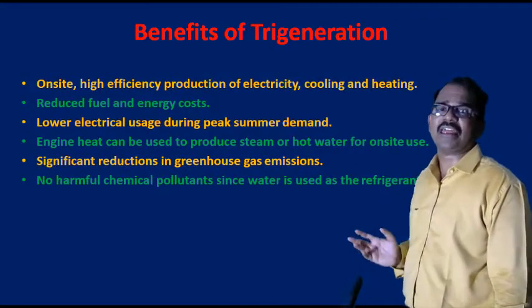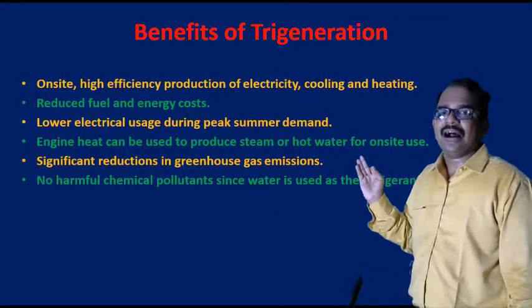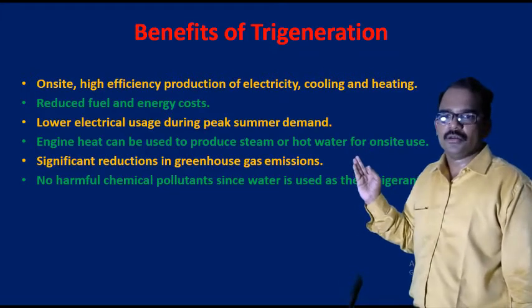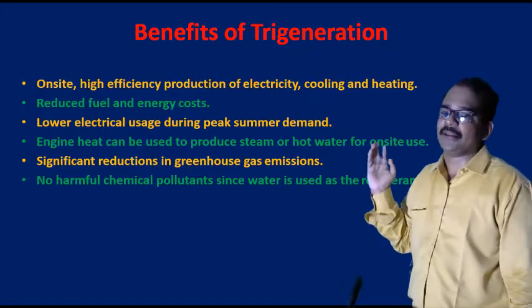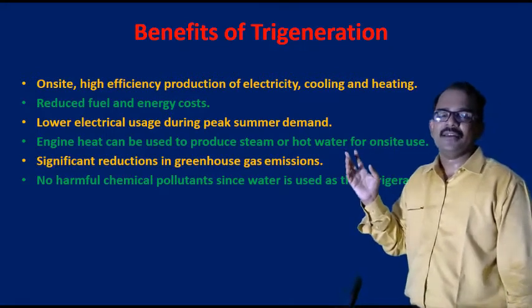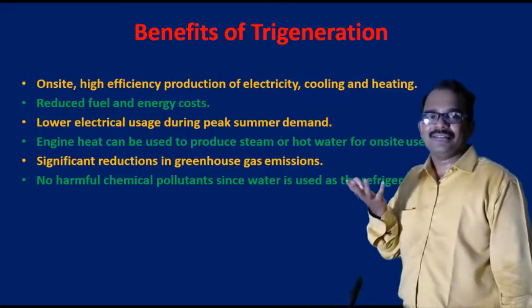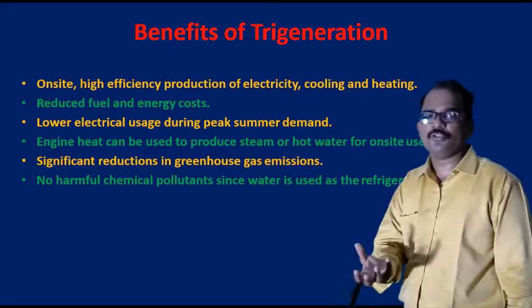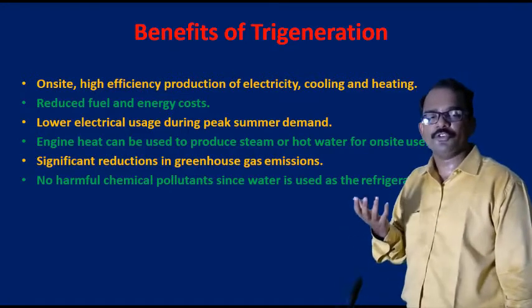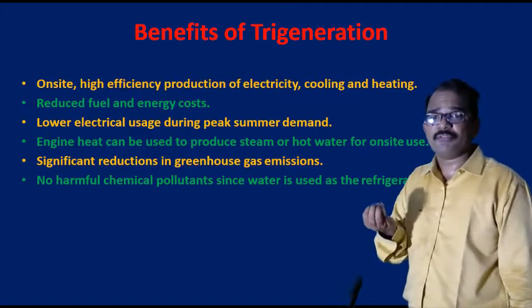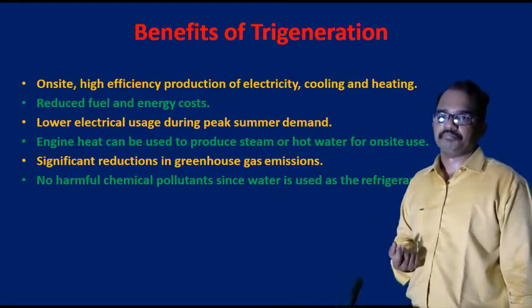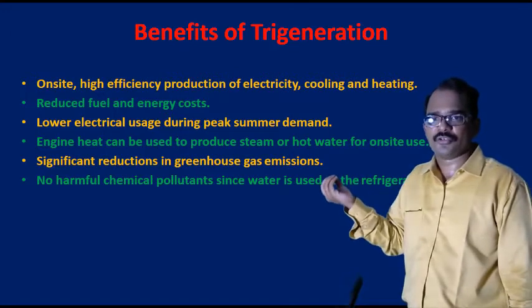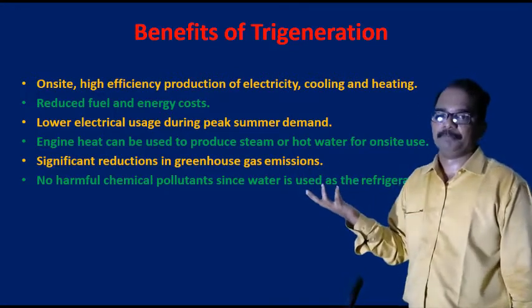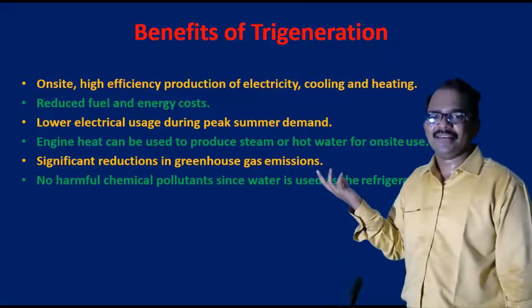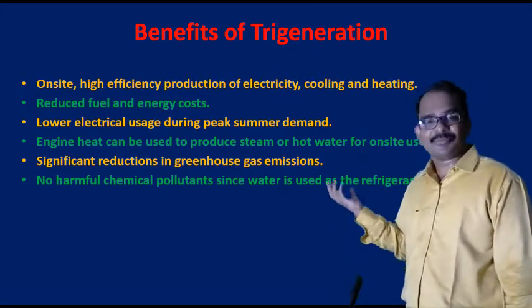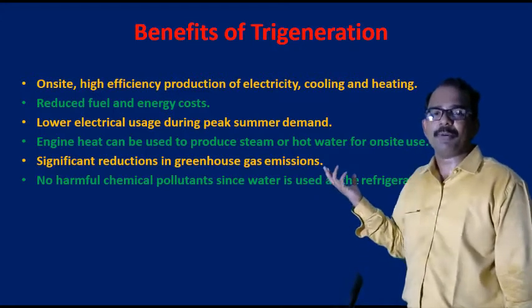So finally, what are the benefits of trigeneration? On-site generation of high efficiency production of electricity, cooling as well as heating from a single fuel, and thereby the amount of fuel required to produce these three independently will be reduced in a trigeneration system. As the amount of fuel got reduced, this will reduce the fuel and energy cost. Right, so lower electrical usage during peak summer demand.